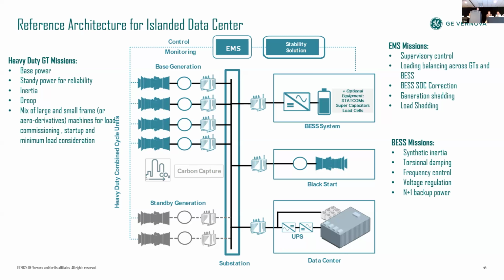And now, because of the aspect related to the load, the system will require, depending on the application, either the BESS or a STATCOM with supercapacitor types of solutions, depending on the application of the BESS itself, right? So in some of the projects that we have been seeing, the BESS has basically a dual role, where it is acting as a reserve to absorb the large transient caused by the AI load, and also is helping to mitigate the variations caused by the load changes.